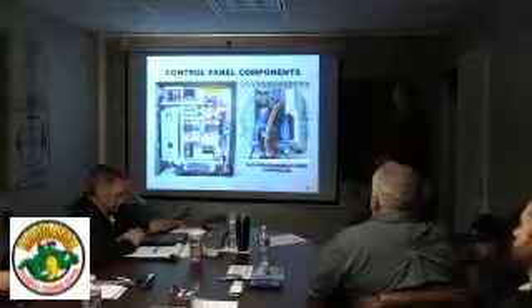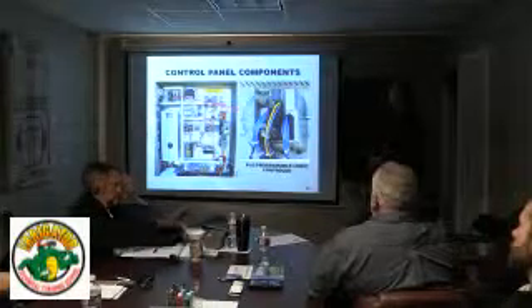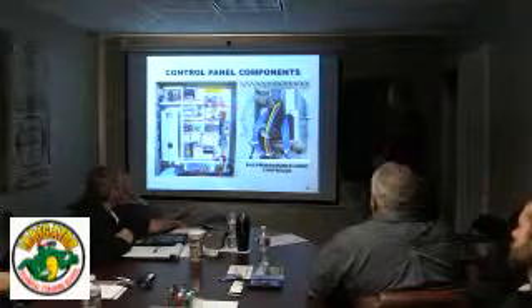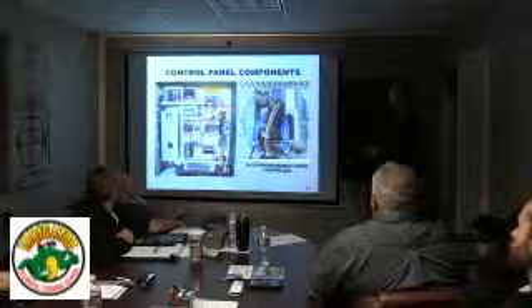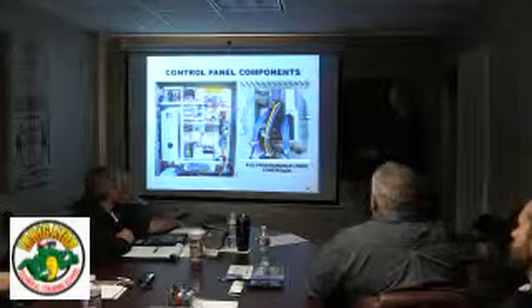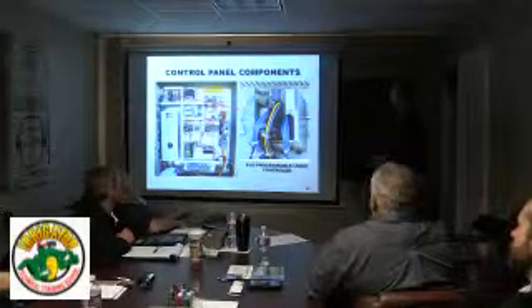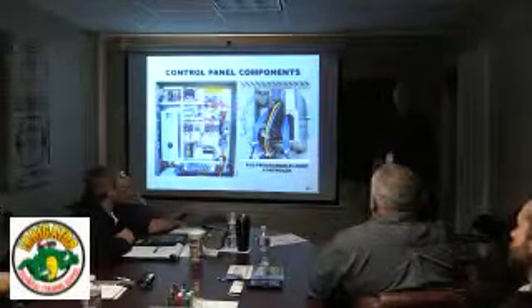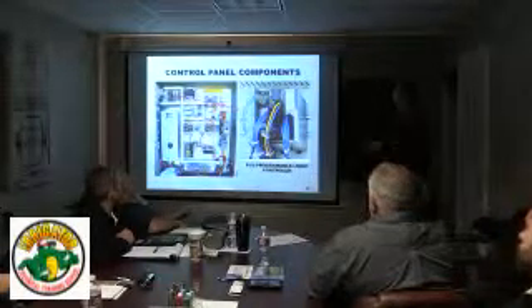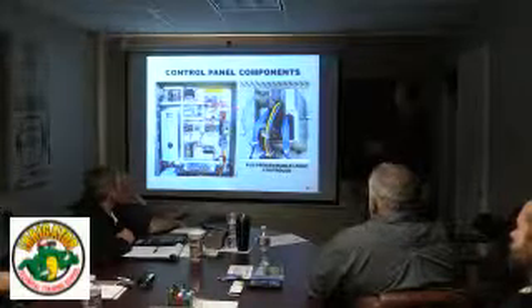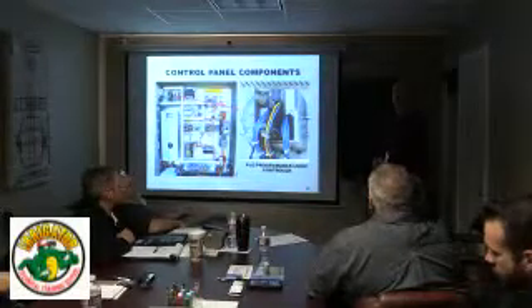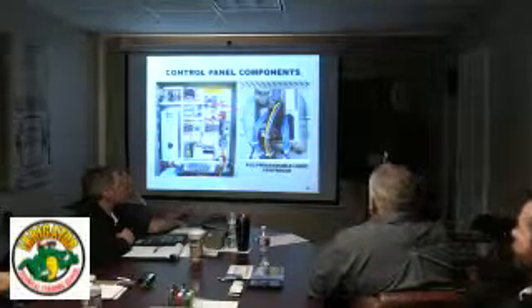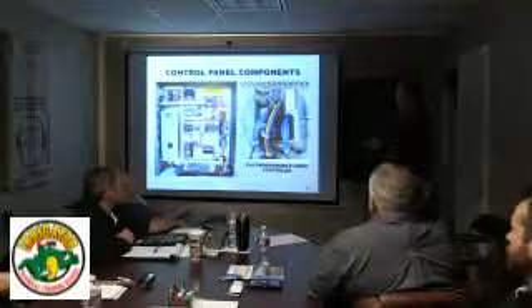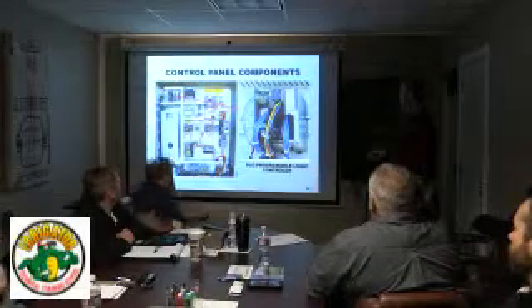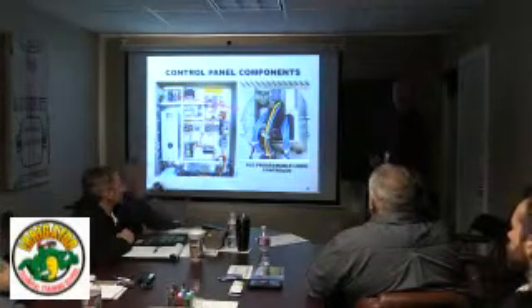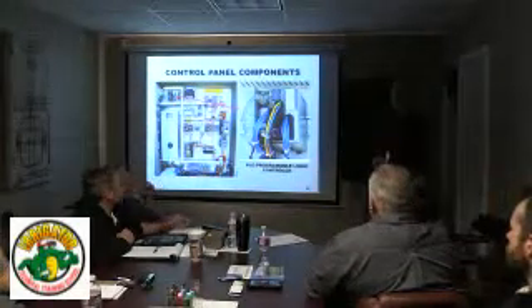Here's a picture of a PLC. This is probably in 95% of our panels. We use this same IDEC PLC. We might only use just this gray brick here, depending on if it has enough inputs or outputs. On this one, what we've done is we've added another DC input module because we needed more inputs. If you notice on our schematics or look at our panels, you'll notice that we use blue wires for inputs to the PLC. That's a 24 volt DC input to a PLC.